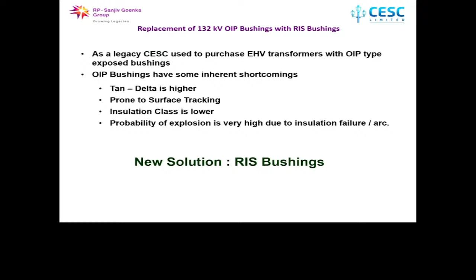So we have shifted to RIS bushings, replacing the old OIP bushings, starting from 2018. The good thing we have found so far is that these bushings are non-hygroscopic, their dielectric loss is very low. We have tested them at site during installation, and they also do not have PD. The weight is very little, about 20%, and of course they are shatterproof.